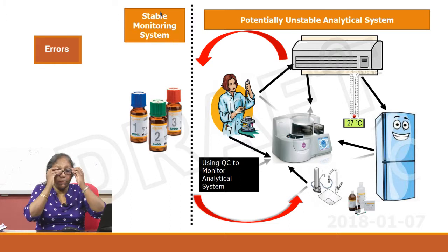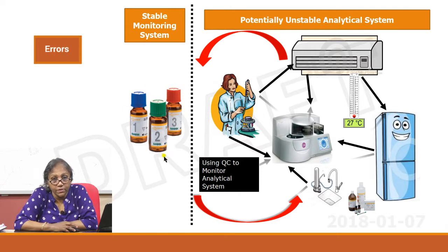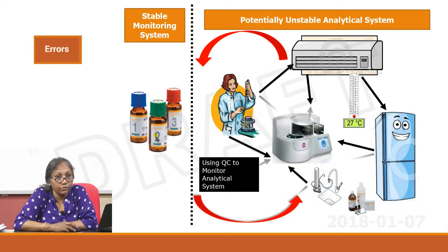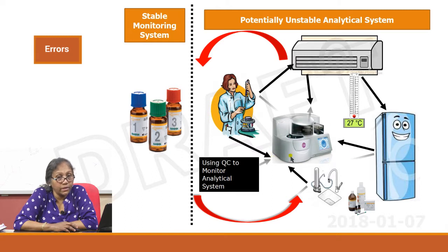There is a stable monitoring system — please underline the word stable. Stable is extremely important. One side of your equation is held stable; how can you balance the other side? You have to make sure your QCs are held stable. We talked about how to maintain your internal controls with integrity. Please follow the rules, because if both sides are not stable, you can never assess your analytical system. We are assuming that your QCs are stable while discussing all these rules and rule violations.